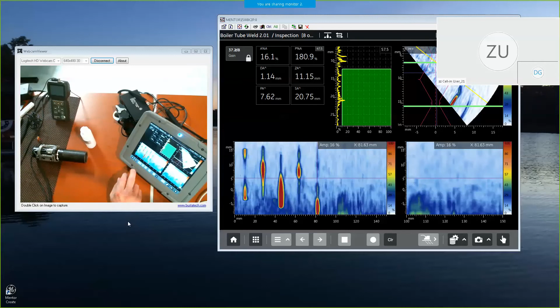Okay, so that's the boiler tube equipment and application that we have available. Again, those scanners are available in 3 different sizes for a range of tubing sizes. We'll clear this and go back to the scanner selection panel. There you can see the different sizes of scanners and probes, wedges that are available.